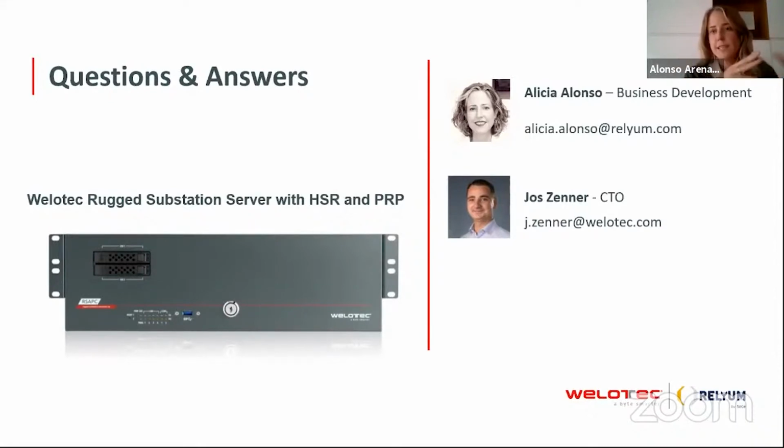So I presented the example of multicast because there you can see that until it goes through all the rings in the network, the second frame is not discarded. So this is the concept. But the RedBox, the node, takes out the trailer, or the header in the case of HSR, and it becomes a normal Ethernet IP frame for the device. So this is one of the goals of the simplicity of the protocol. Okay, thank you very much.